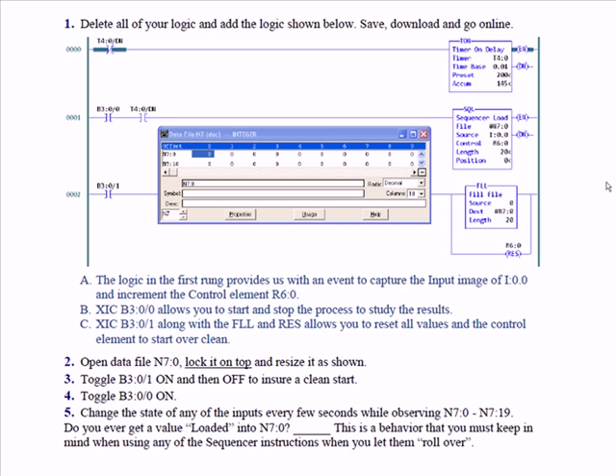Sequencer load instruction. We have three rungs. The first rung is a free-running timer. It's running on a time base of one hundredth of a second. It has a preset of 200, which means it's going to run for two seconds.